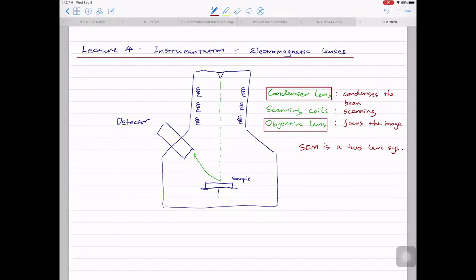Any questions about the instrumentation? A student asked: 'I didn't quite understand the scanning coil's purpose.' If we only have the condenser lens and the objective lens, then what we see is just one disk or spot on the specimen — and that's all. In order to form an image, we need the scanning coil to raster, to deflect the beam so it scans the specimen. At each pixel, you generate information collected by the detector. Without the scanning coil, it would just be one focused narrow beam on the specimen.